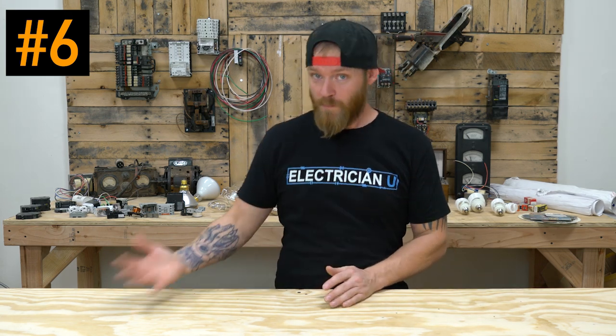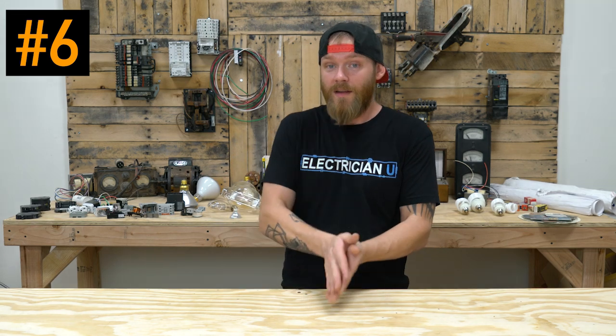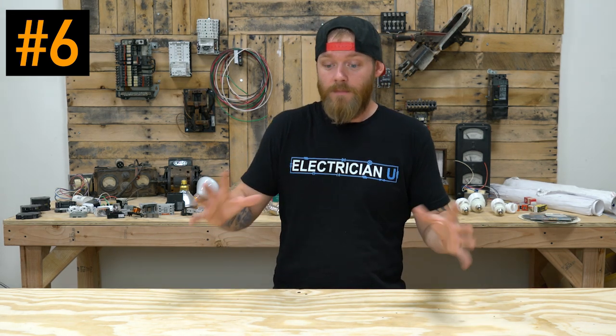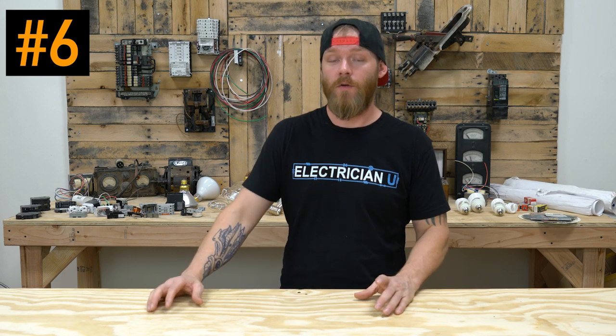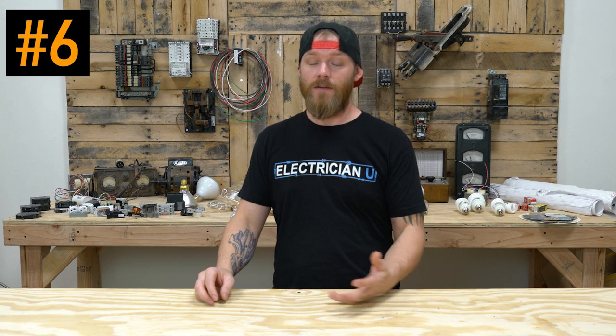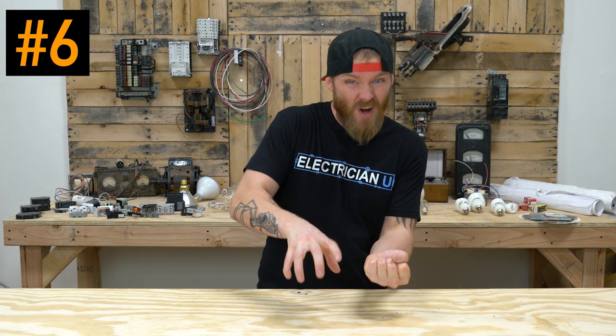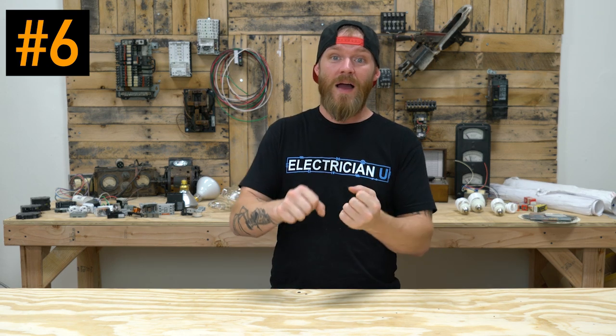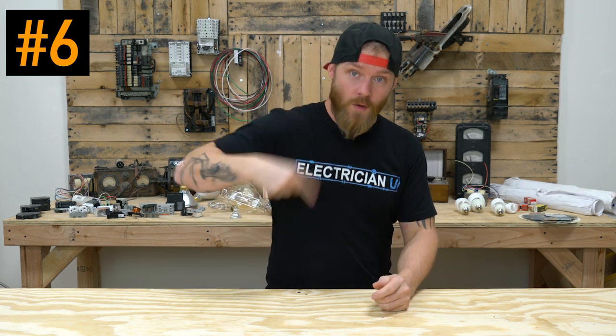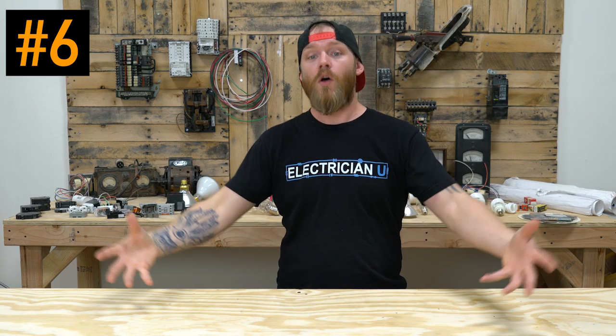This is why breakers become really important, because certain conductors can only handle a certain amount of heat and a certain amount of current going through them before they get really hot and start melting the insulation. So overload just means that the equipment itself is overloaded. Some things bind up, like you might have a motor that has bad bearings in it, or that is stuck on something and it's trying to spin. It's still making a complete circuit, but because it's not spinning, it's bound up, which means it's allowing more current to go a lot quicker. So that is an overload.